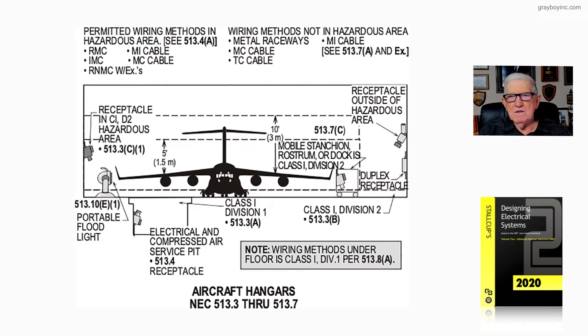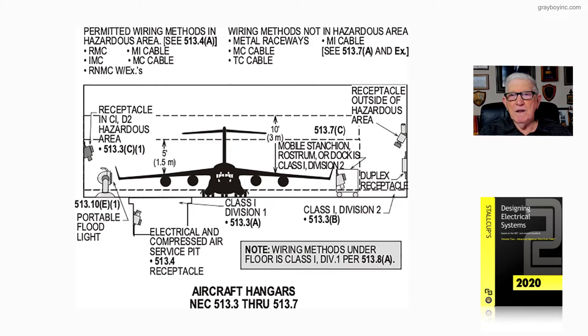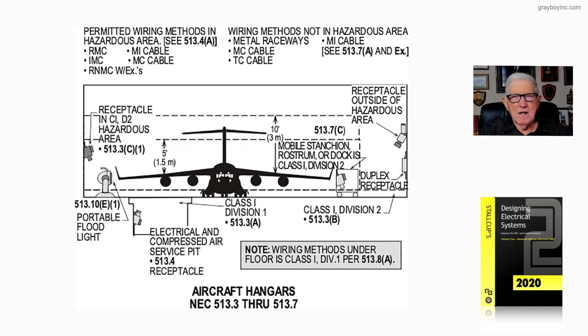For wiring methods that are not in the hazardous area, you can use metal raceways, MC cable, TC cable, MI cable, and any of the exceptions to 513.7a that you would review. So your key sections here are 513.4a, 513.7a, and the exception.